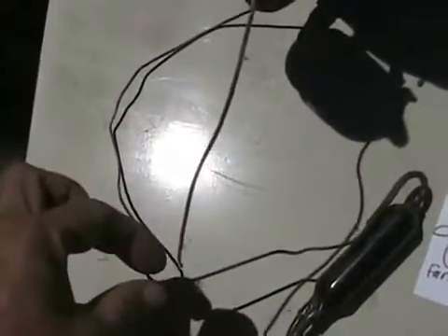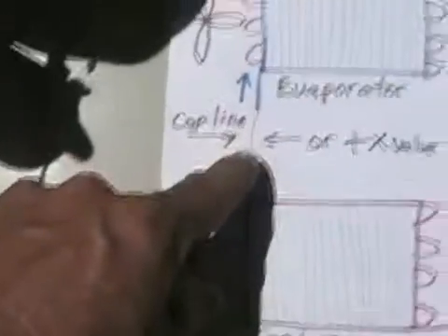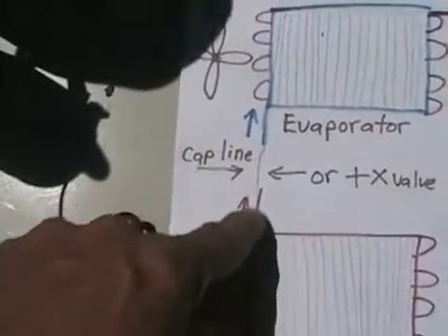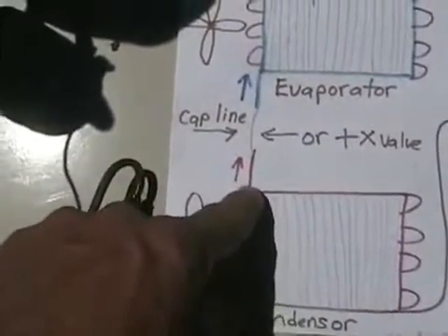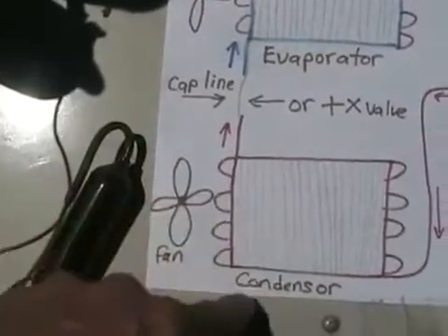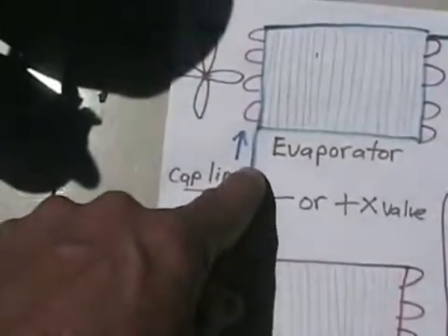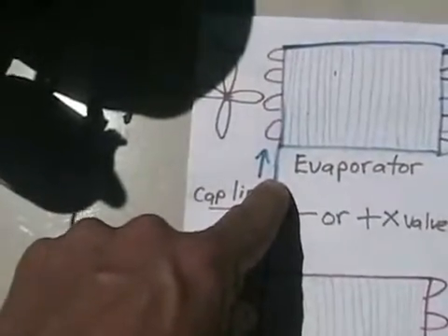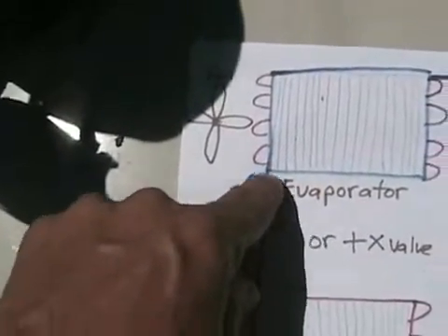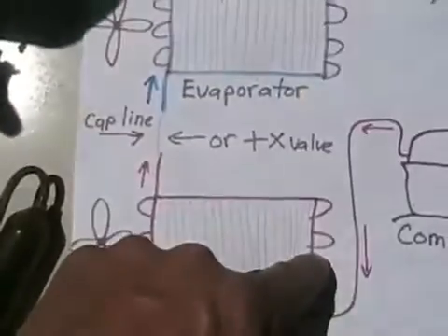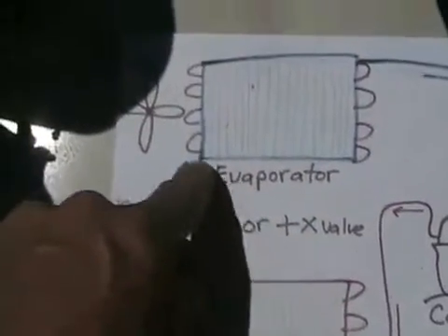The tube looks just like a wire, but it's actually hollow. The reason you do have this long, skinny, restricting tube that forces the Freon through very difficultly is so that it can create back pressure, so we maintain liquid Freon on the condensing coil. By the time the Freon goes the distance of that tube and gets to the evaporator, it is all the largest diameter tubes on the air conditioner, much larger than this tube.